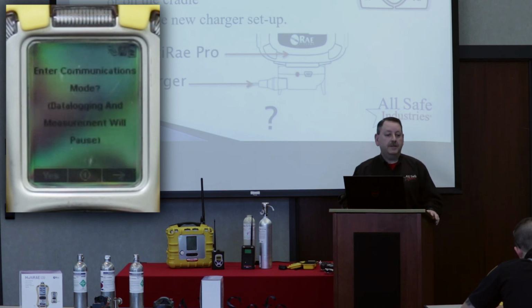What's the last page say? Enter communication mode. So everybody go ahead and say yes to that or select it, because I want to point something out to you. Enter communication mode has nothing to do with it being a wireless instrument. That's happening all the time. Communication mode is for maintenance. And so it's asking you on the next screen, do you want to connect to a PC? So meaning we'd use a cable to our USB port and we'd connect it to a computer. Or do you want to connect to an AutoRae 2?